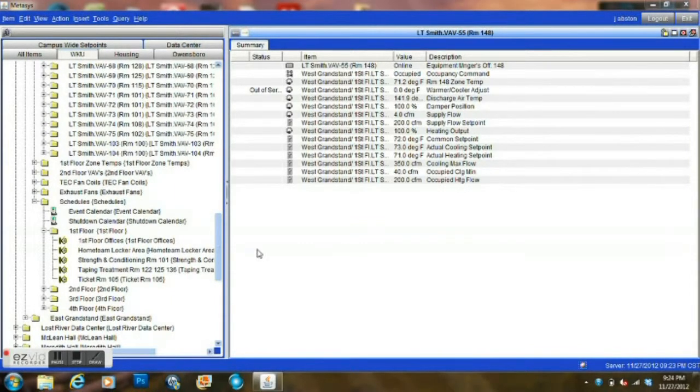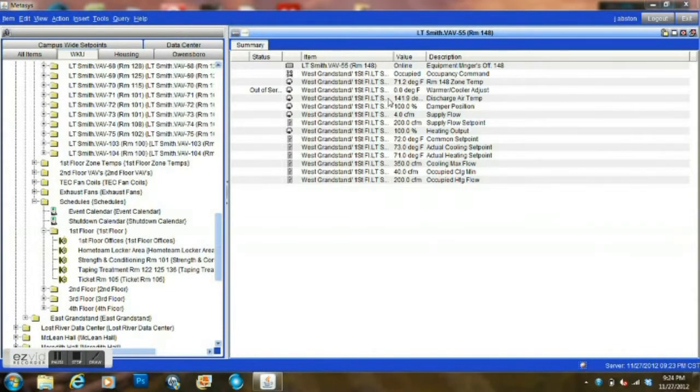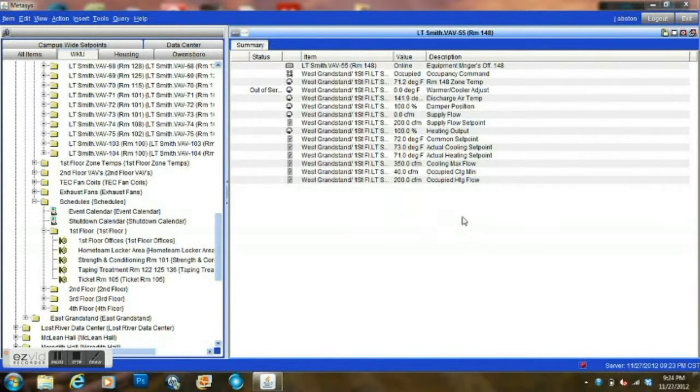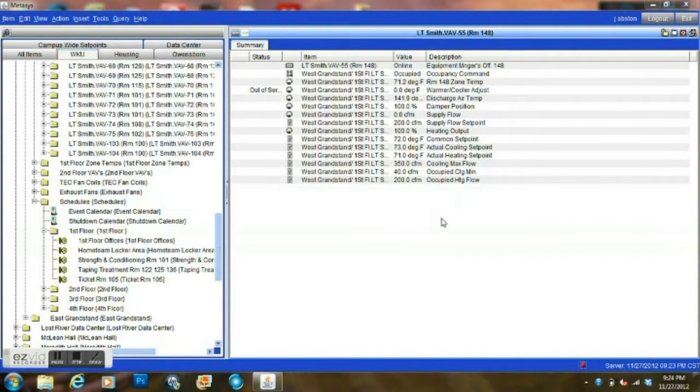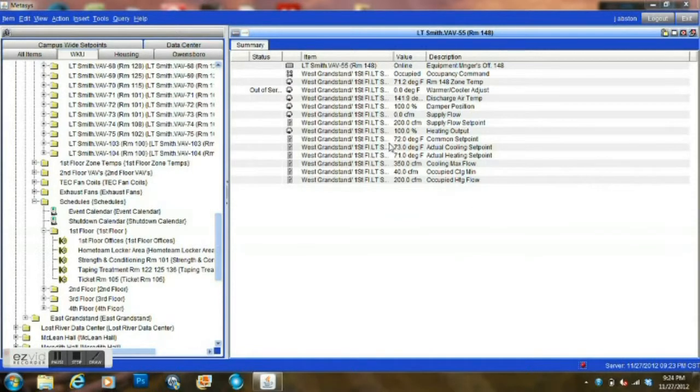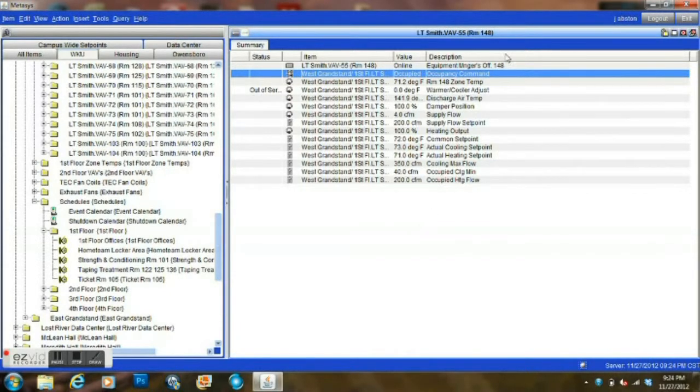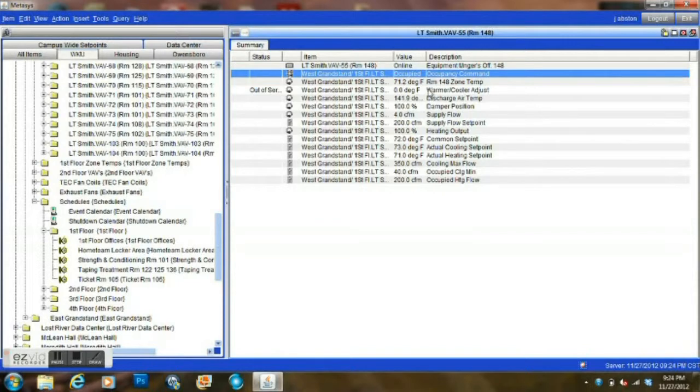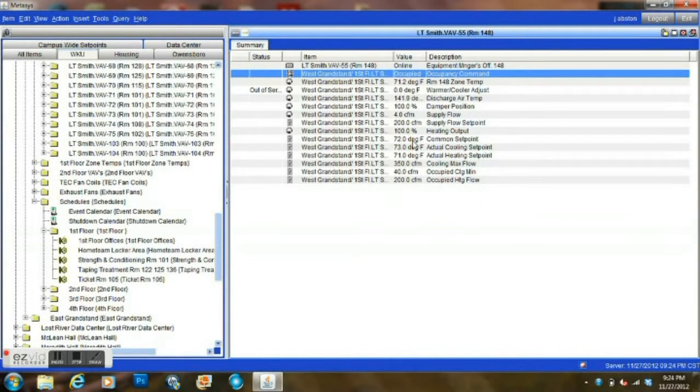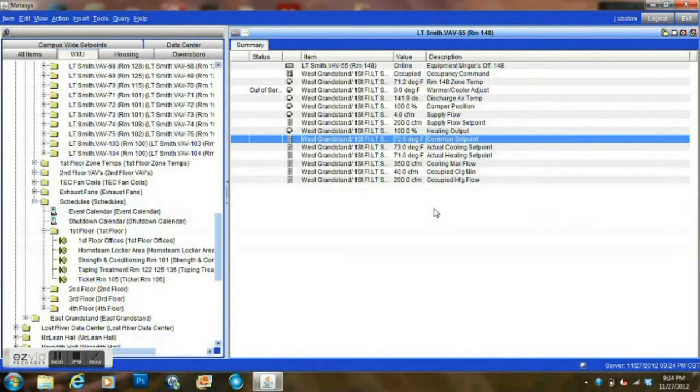One of the things that we're going to look at here first of all is we have one of our VAV rooms. The point that turns the VAV on for it to control our space temperature to our set point is the occupancy command. If the room is occupied during the daytime, it will be on to maintain the particular room set point, which in this case is 72 degrees.